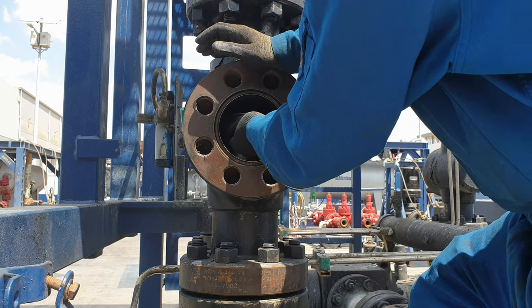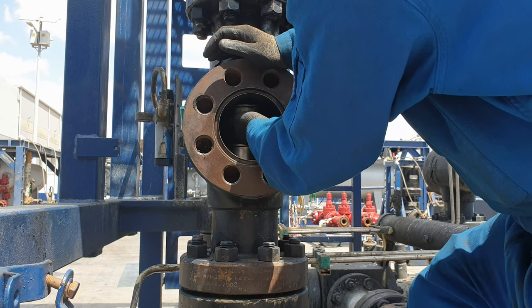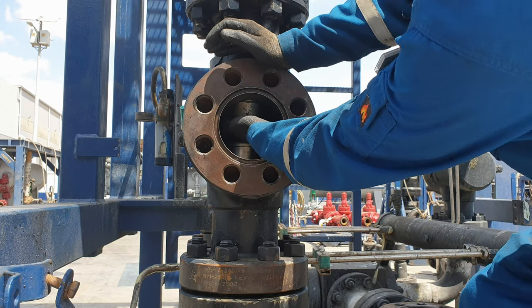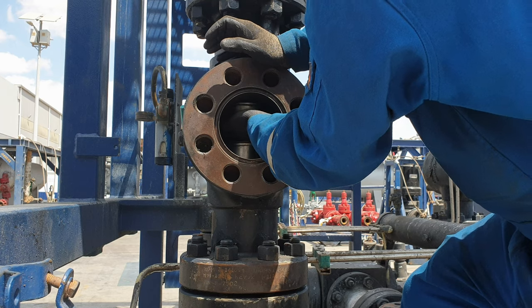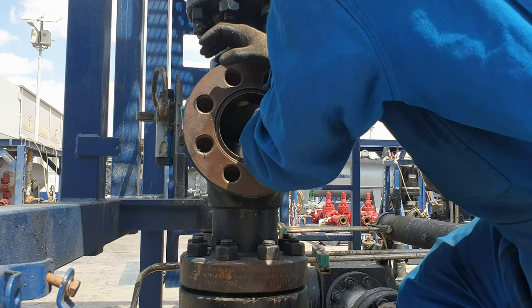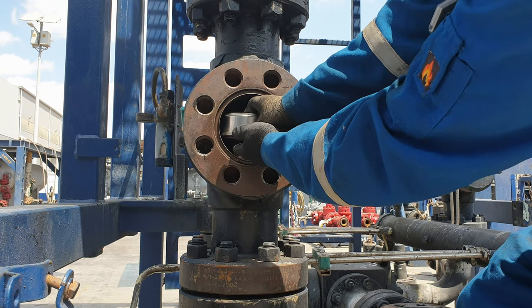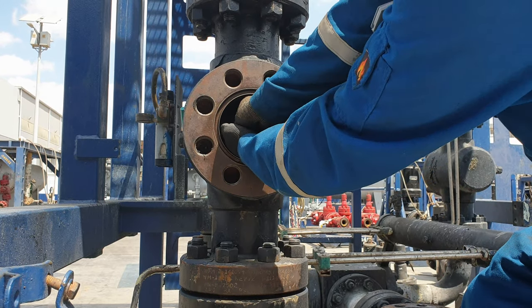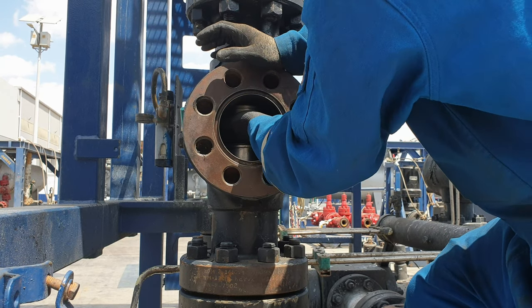During assembly, the gate valve is in a vertical position, like the steam exchanger and sand filter. It is very difficult to hold the upper sealing assembly against gravity, and actually there is no shoulder inside the valve cavity to help you. So, we try many times to hold the upper sealing assembly in position by using some grease. This process takes much more time, and the operator's hands usually work in a pinch point hazard.